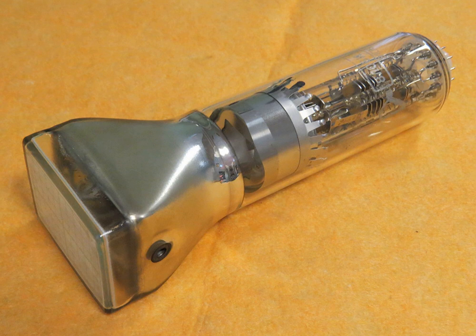The trigger section controls the start event of the sweep. The trigger can be set to automatically restart after each sweep, or can be configured to respond to an internal or external event. The principal controls of this section are the source and coupling selector switches, and an external trigger input (ext input) and level adjustment.